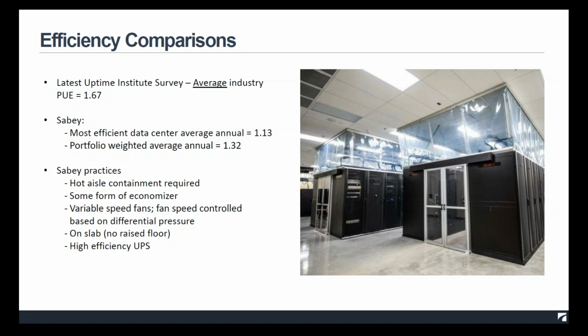So since 2008, we've required hot aisle containment. So our designs are based on hot aisle containment. All of our data centers use some form of economizer, and the form we use may vary depending on the climate. So in Seattle, we use a lot of airside economizer, direct evaporative cooling. In Central Washington, we use a lot of indirect evaporative cooling. And we use waterside economizer in New York. So that's just an example of the different economizer strategies one may use in different environments. But in each of them, we're using some form of economizer in our data center.